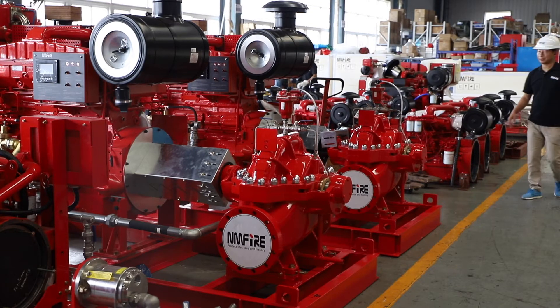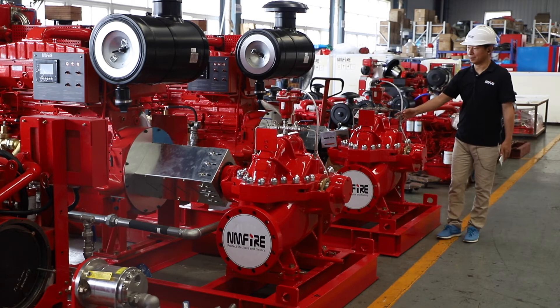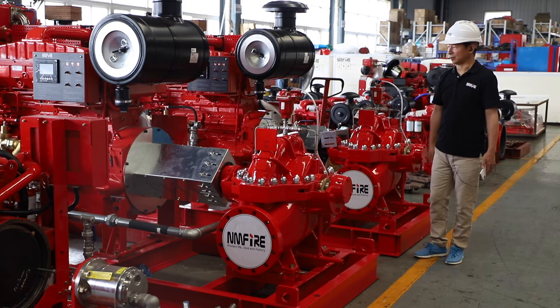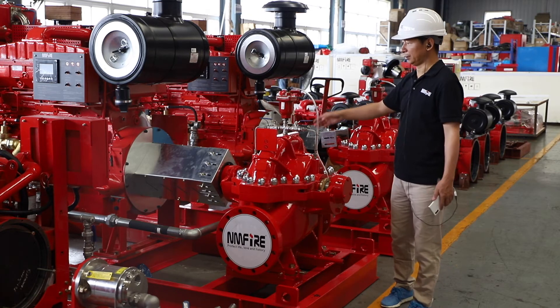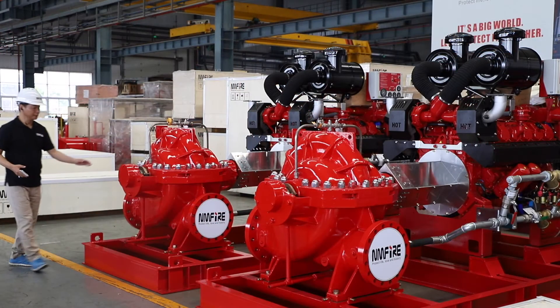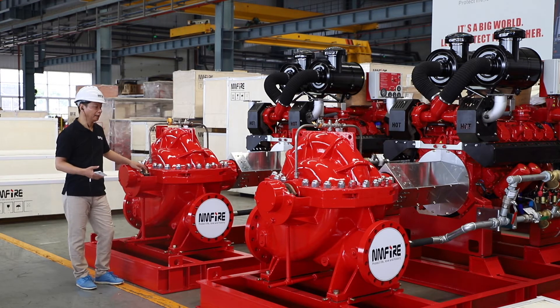For our split case pump at smaller flows — this one is 2,500 GPM — we usually use the high-speed engine driver running at 2,950 RPM, with a 3,000 RPM engine driving the pump. This is mainly for commercial firefighting. You can see these two 5,000 GPM diesel engine-driven UL/FM fire pumps, which were used for an airport in China.